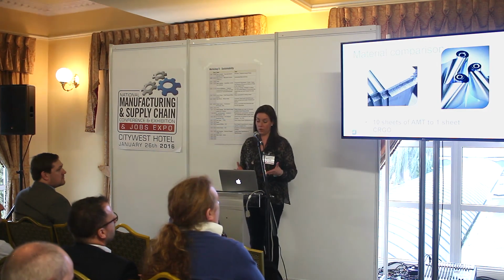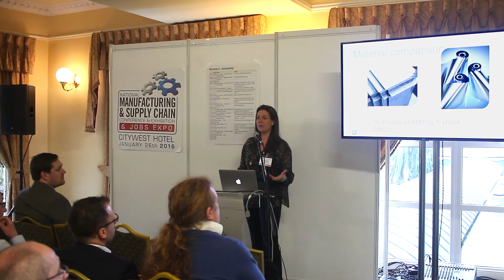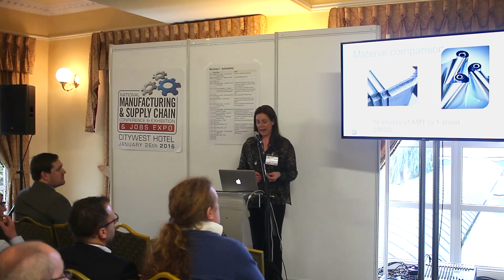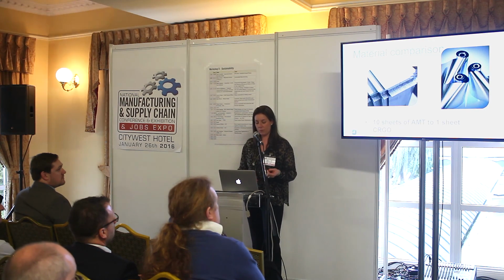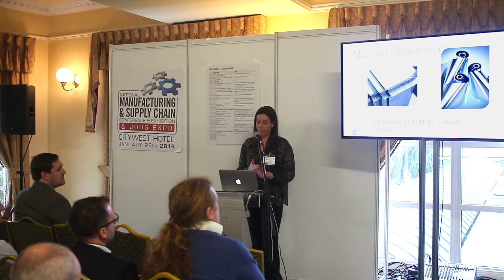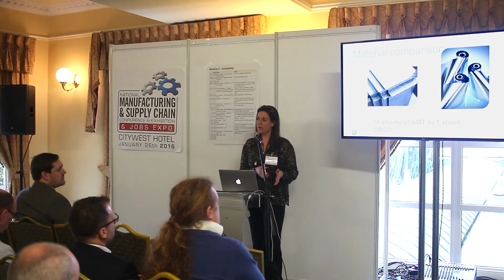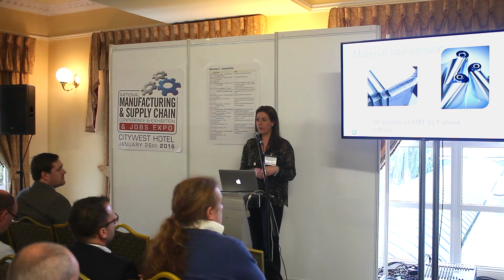The actual manufacturing process of amorphous transformers is quite different. On the left you see a standard transformer product, where the core steel is in laminations. The amorphous core on the right takes about 10 sheets to every one single sheet of core steel. It really is a different manufacturing process, far more delicate.